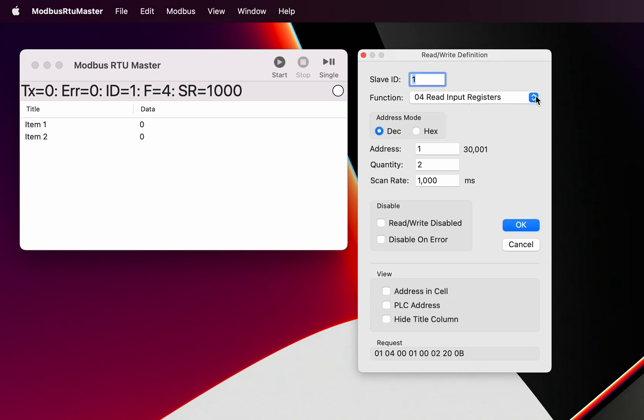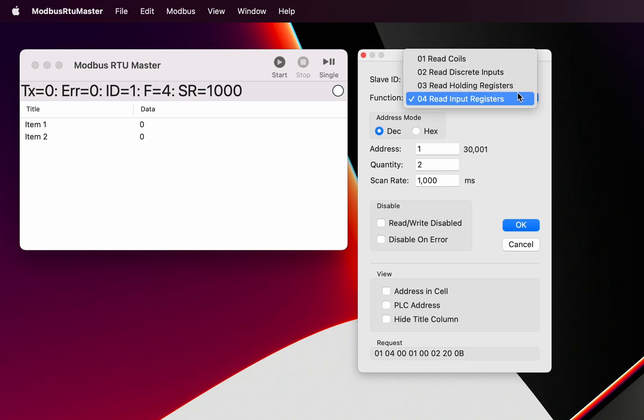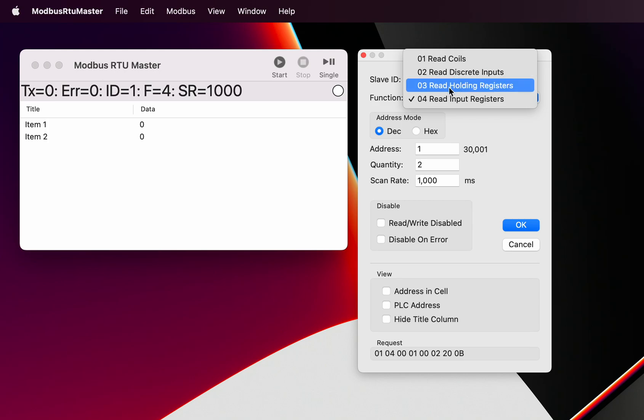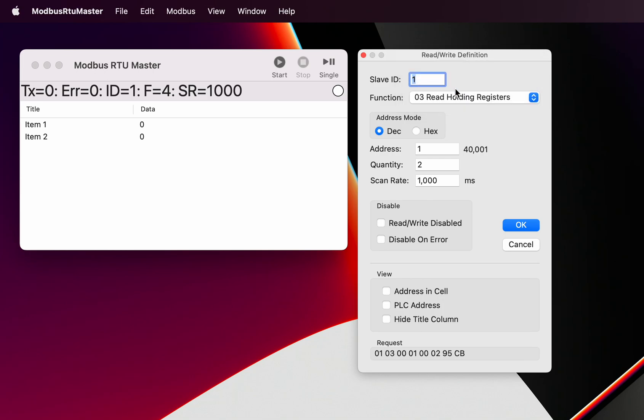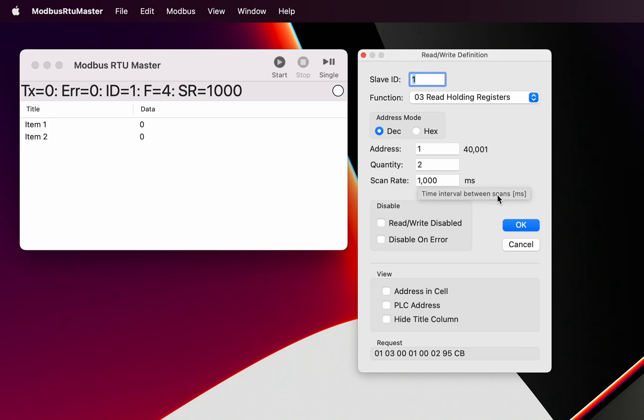At the moment we've got a number of different Modbus functions. If you want to read from the holding registers, for example, we've got the ability to define which address, the start address, and how many Modbus registers you want to read. Modbus registers are always 16-bit, so here we define how many 16-bit registers we want to read.